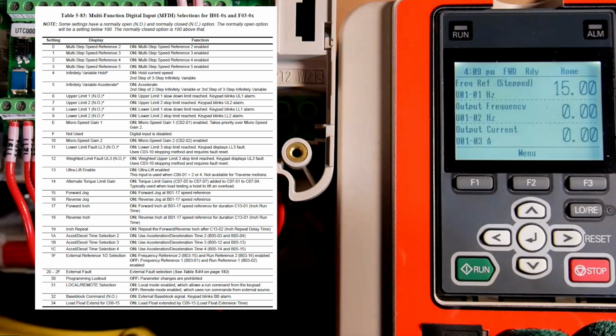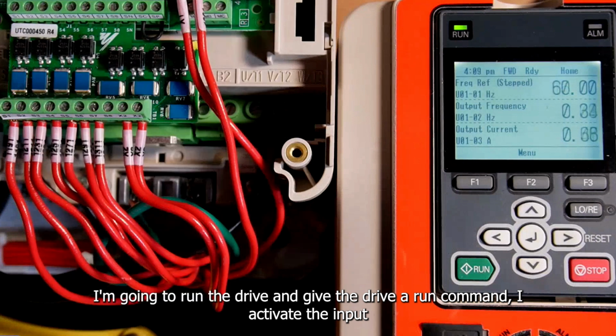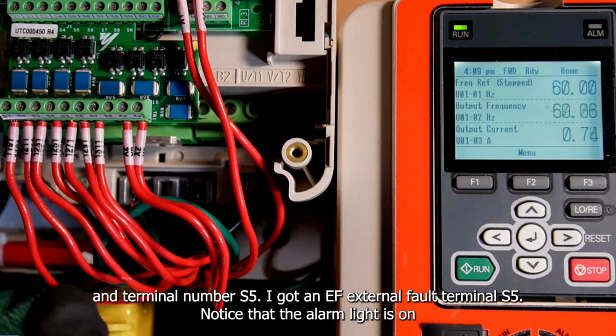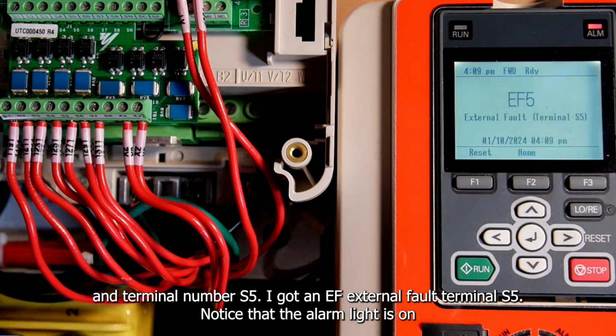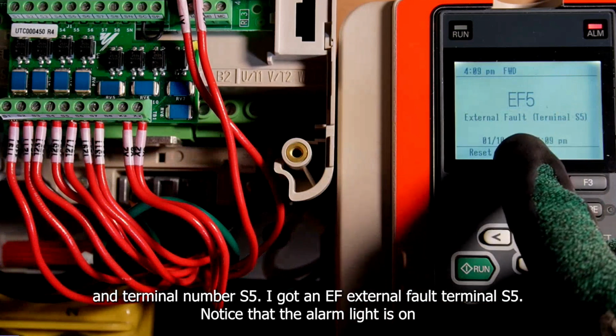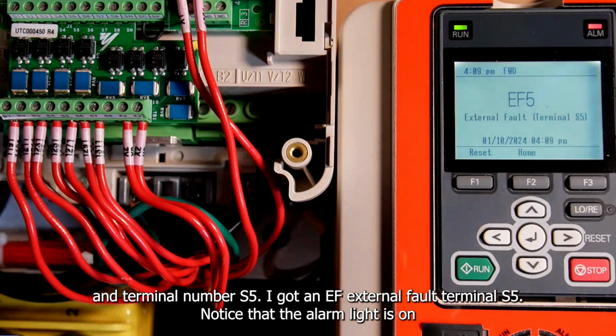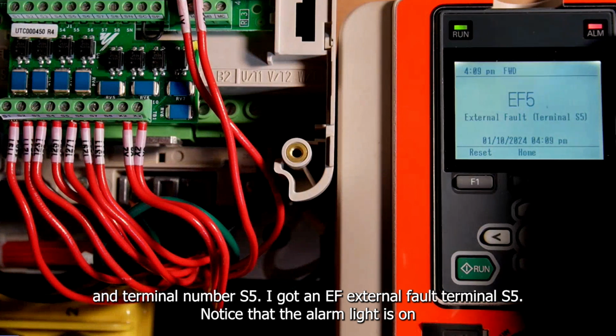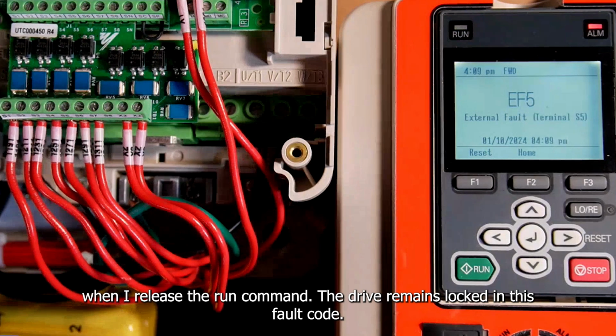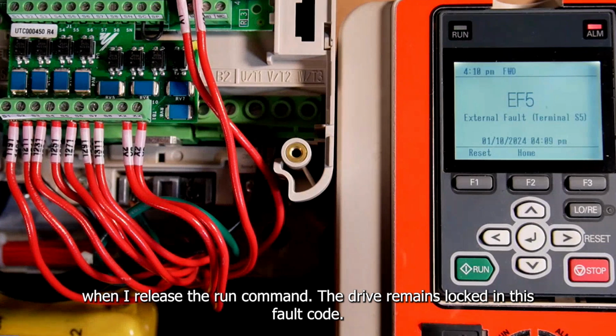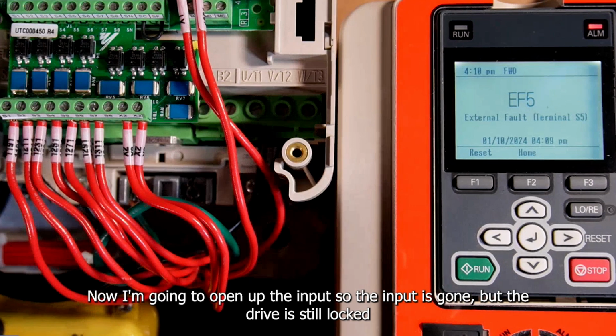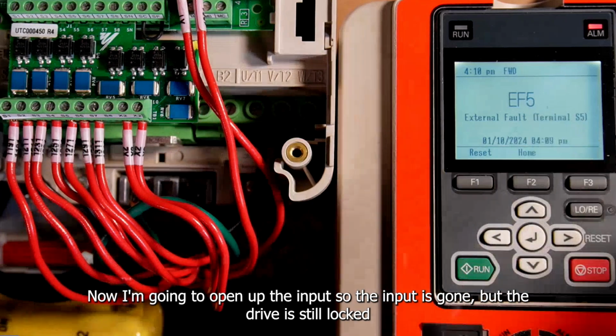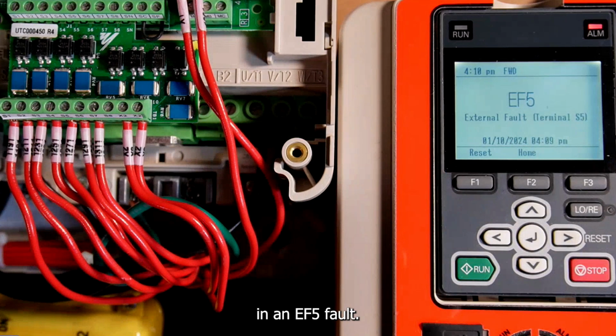So now I'm going to run the drive. I'm giving the drive a run command. I activate the input on terminal number S5. I got an EF, external fault, terminal S5. Notice that the alarm light is on. When I release the run command, the drive remains locked in this fault code. Now, I'm going to open up the input. So the input is gone, but the drive is still locked in an EF5 fault.